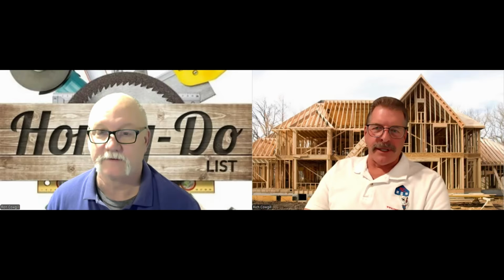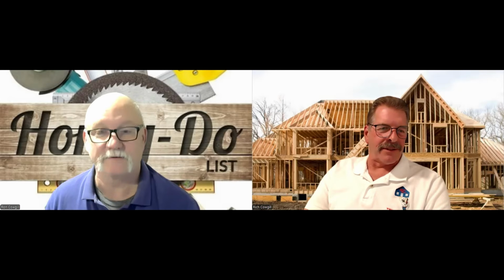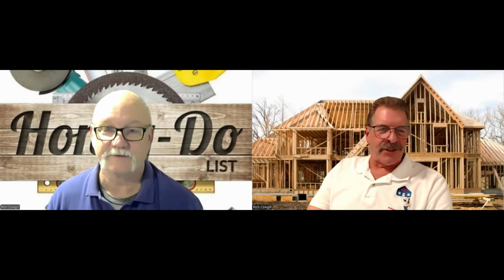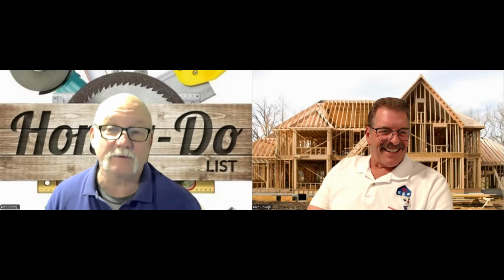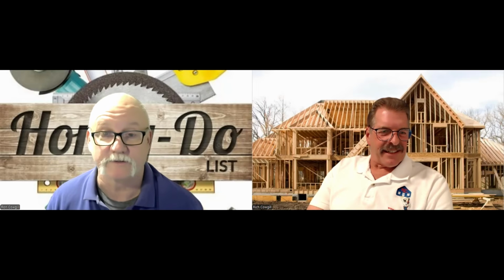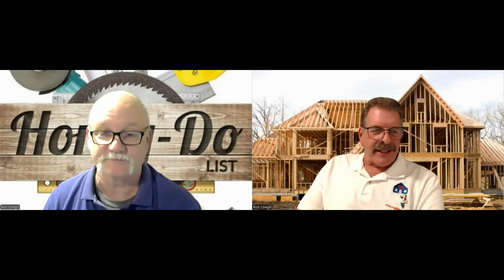Right. And thermodynamics, more or less. The more the AC runs and tries to dry that house out, the more humidity gets sucked in from outside. So even the inspector that walked in there should have asked, why do you have insulation inside the building envelope? Maybe it was just scraps and they didn't want to throw it in the dumpster. The dumpster was full.